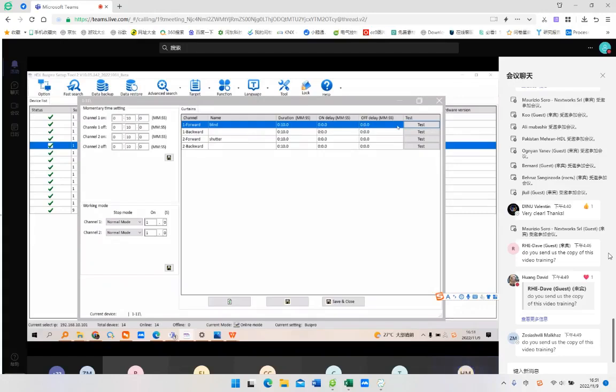And always remember, as this curtain module cannot read the time the curtain takes to be fully opened, you have to measure the time it takes to fully open the curtain and enter the duration. It is very important.